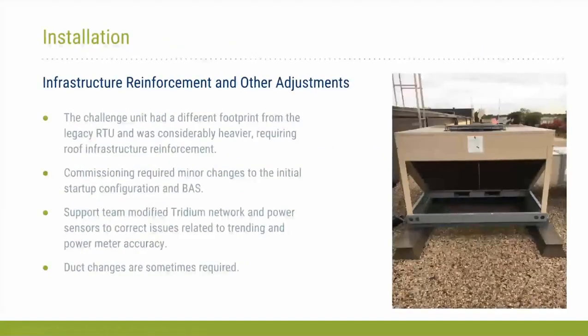And I'm going to cover some of the installation details, and you'll probably hear more from our GSA staff from that building, additional details. Each installation is going to be different. However, there are a few things that you can consider if you're considering these types of units. The units are generally heavier than the units that you're replacing, and may also have a different footprint than the legacy units. So you need to be aware of that. Because the high performance units have advanced controllers, and some of the installers may not be familiar with commissioning, it could be a little bit tricky or a bit of a challenge. However, widespread deployment of these units should alleviate this issue over time.